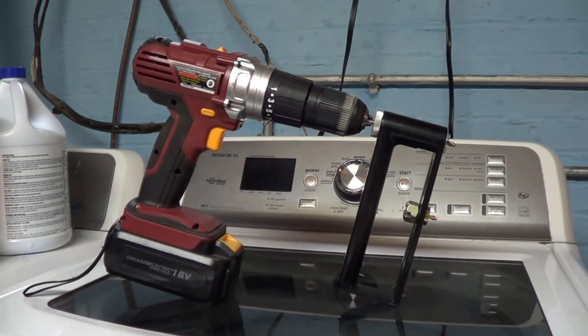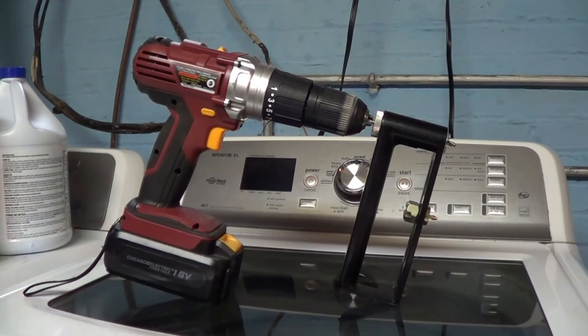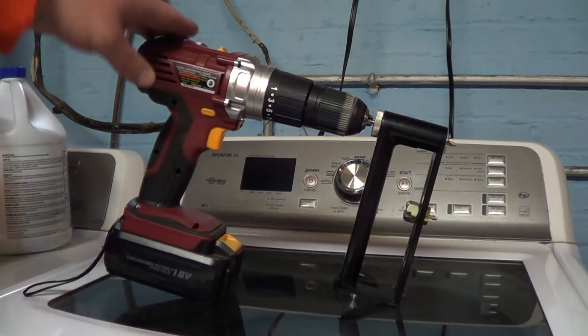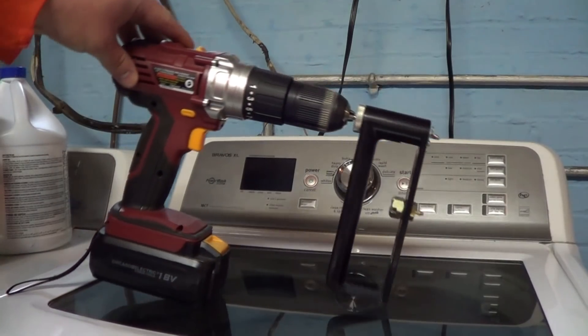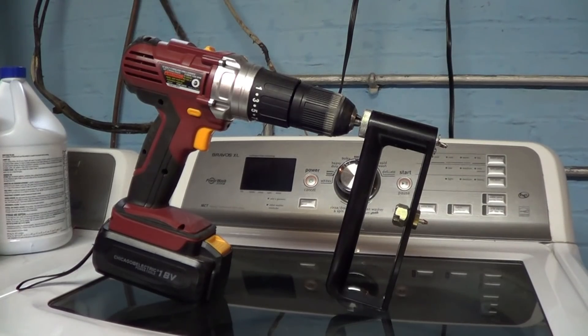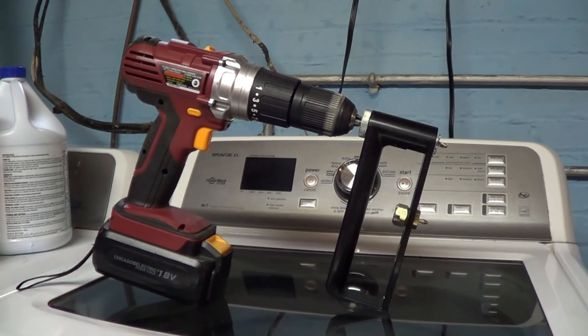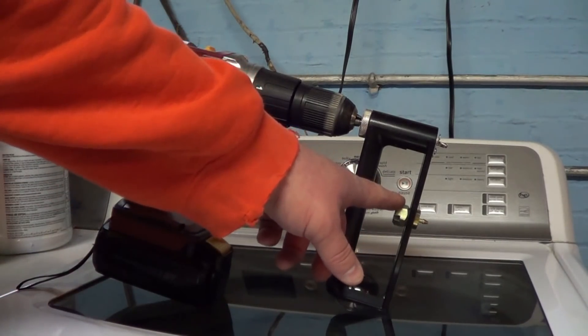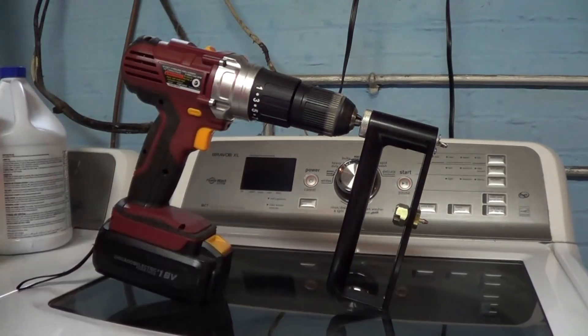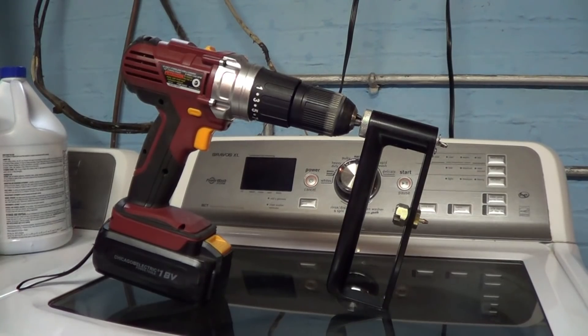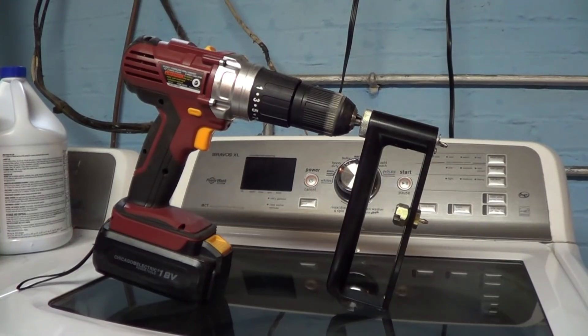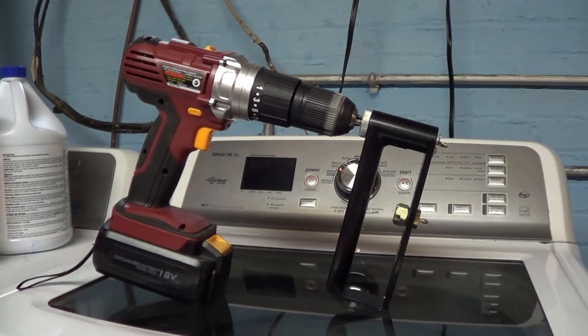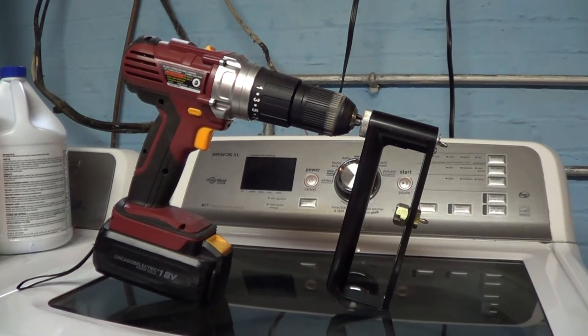I could have made my entry into the ductwork using a set of tin snips, which I actually do have, although they're the ones you get at Harbor Freight, so they're probably not actually worth having. But why would I go to that much trouble when I have this almost totally awesome Malco HC1 hole cutter? One of my instructors told me of this and we got to use one in the classroom. Suffice it to say, it is an amazing tool for making round holes in the ductwork. But unfortunately, since I didn't set it up in the classroom, I had to learn a hard lesson about it just now. This little adjustment right here is what sets your ductwork size, the hole that you're going to make. And unfortunately, if you really don't crank that bad boy down, and apparently I didn't crank it down enough the first time, it'll creep on you and your hole ends up getting bigger. And you might not realize that until after the fact, which I didn't, but it's nothing that a little sheet metal or some furnace tape can't ultimately fix.